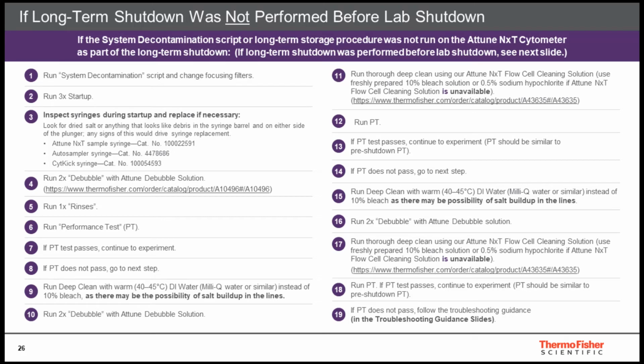Following the decontamination script, keeping with our 3, 2, and 1 rule, run 3 startups, 2 debubbles, and 1 rinse to rinse out the system and make sure it's purged of all the air. Next, run the performance test using the performance tracking beads.